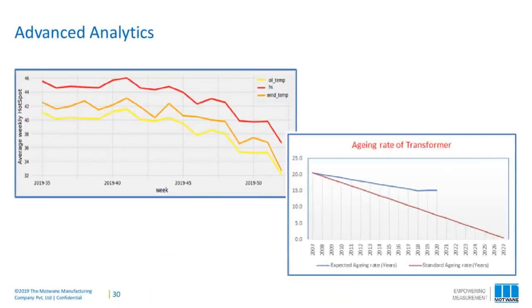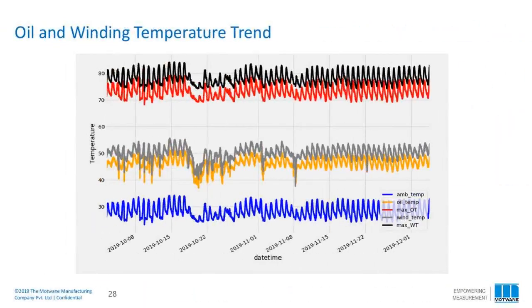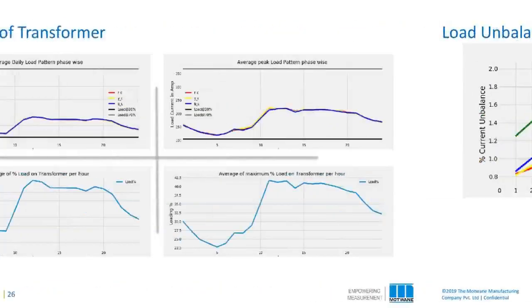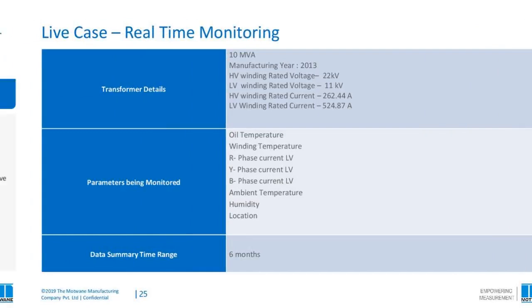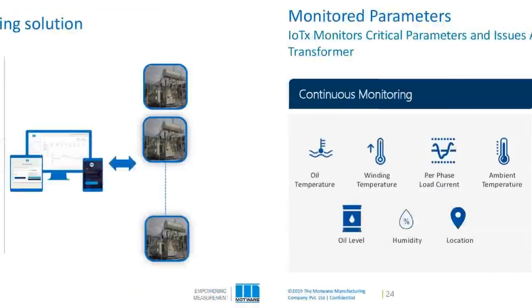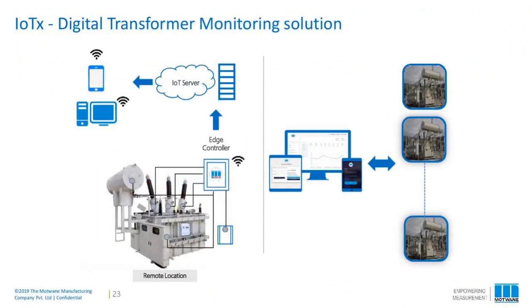Again, the idea for this is to keep it highly customized and granular, so that when you're analyzing and reading this data, you're able to look at it for very specific transformers at a very specific point in time, because there could be a lot of data being captured at different points for different assets or different sets of transformers. So the short answer to your first question is yes, you would need one device per transformer.